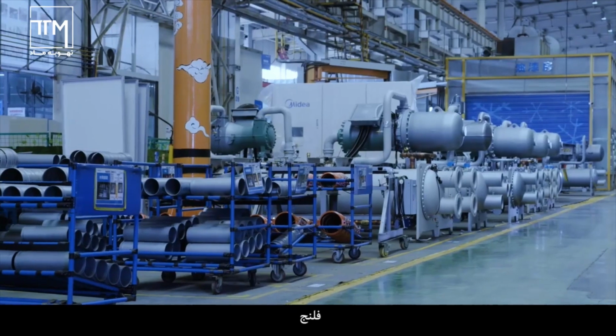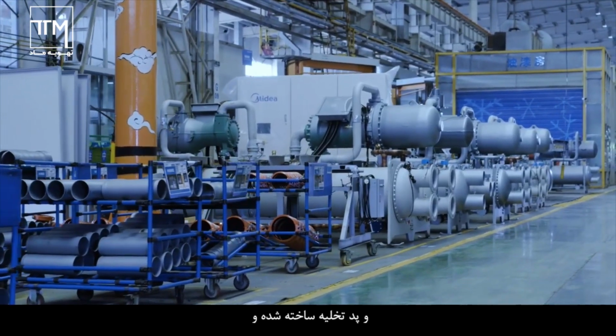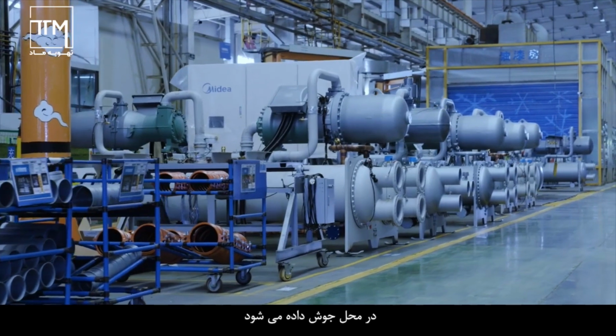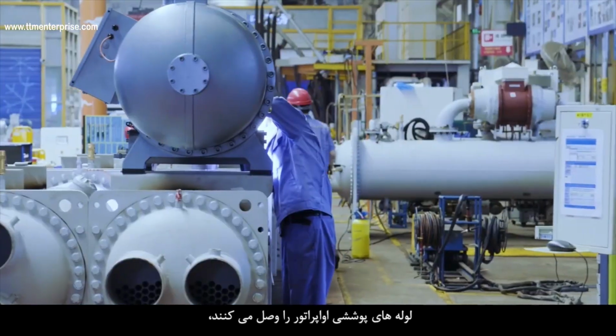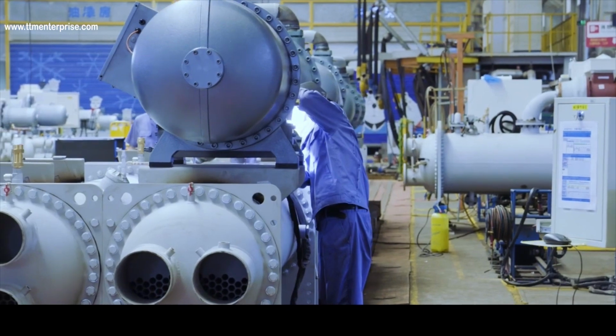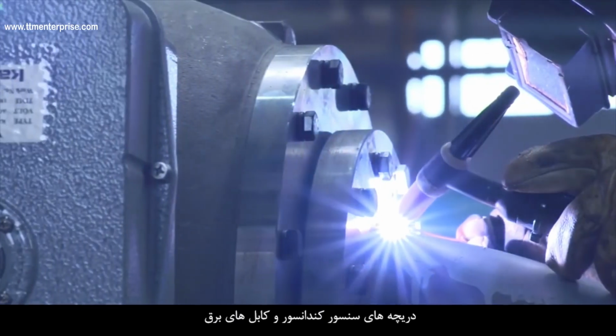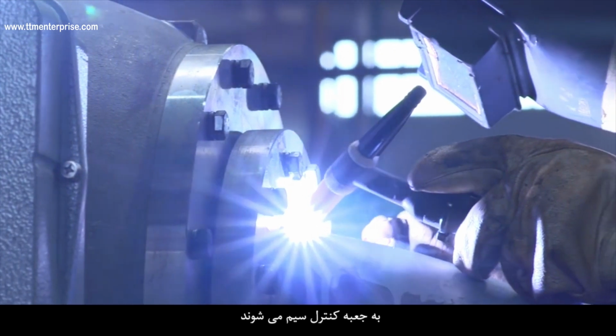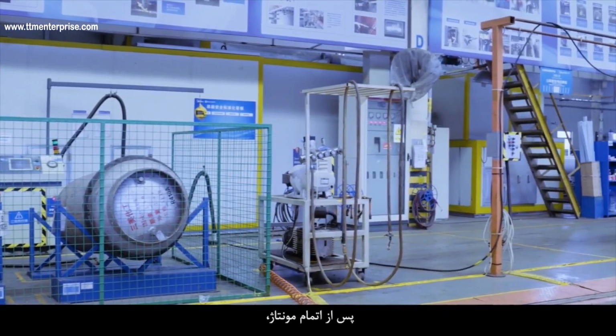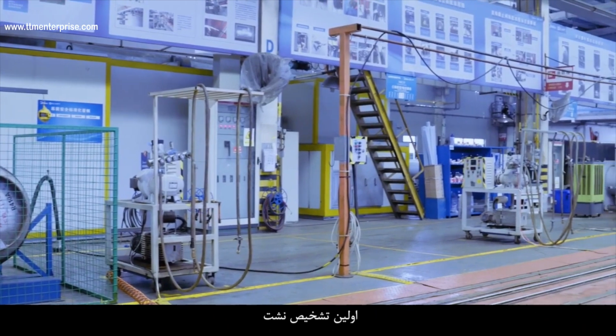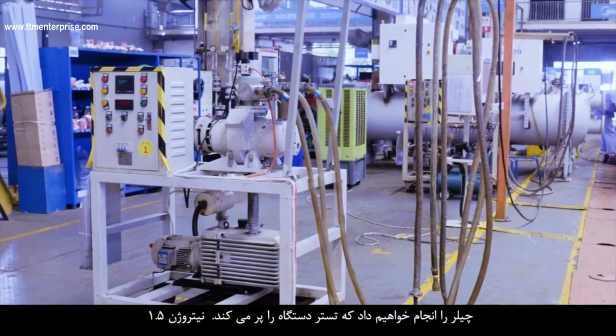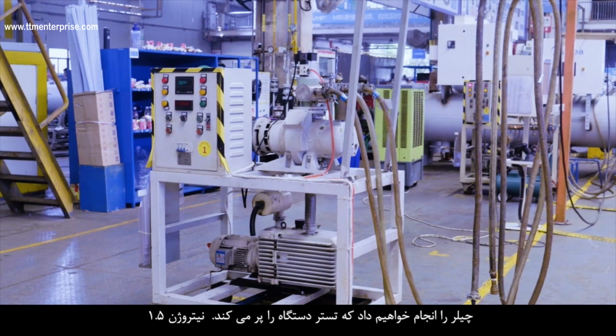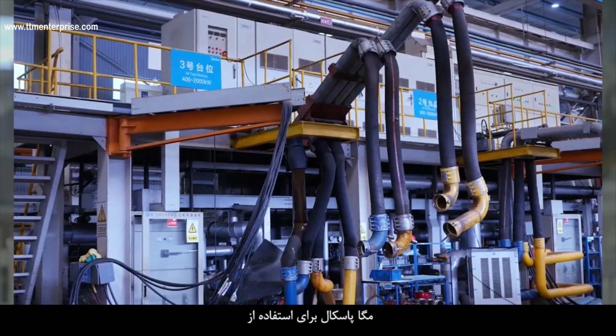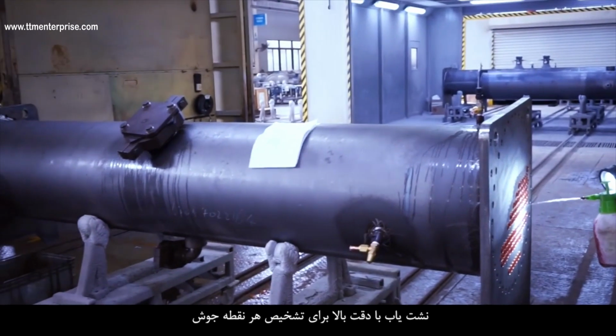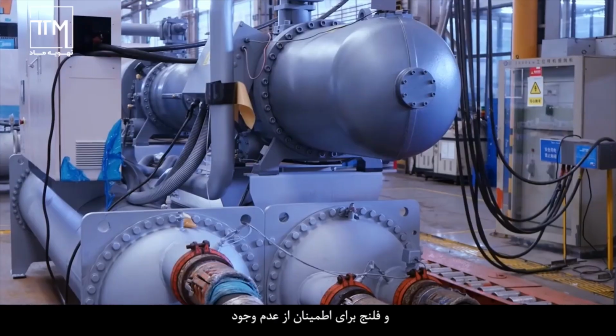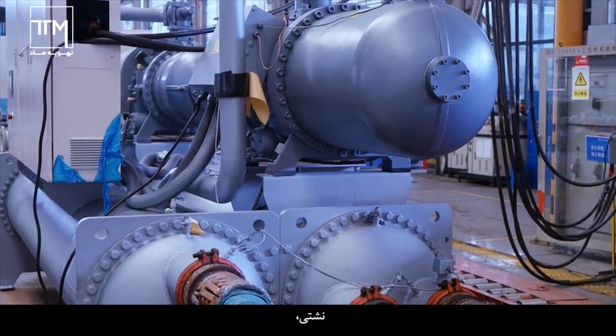The compressor is installed. The flange and discharge pipes are fabricated and welded into place. Copper pipes connect the evaporator and the condenser, and sensors, valves, and power cables are wired to the control box. After the assembly is finished, we will carry out the first leak detection of the whole chiller. The tester will fill in nitrogen of 1.5 megapascal and use the high precision leak detector to detect each welding point and the flange to ensure there is no leakage.